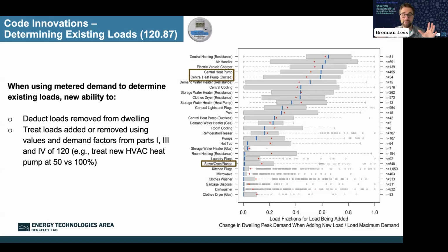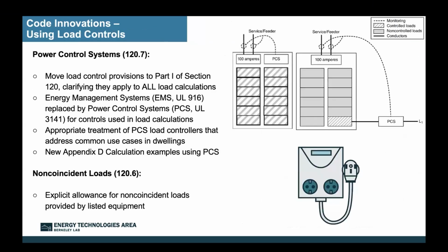Rather than having to add your new heat pump at 100% of its nameplate rating, we can look back at that section 120.87 we were just talking about and instead add it at 50%. Same goes for if you're adding a new electric cooker: instead of adding it at 12 kW, we can add it at 6 kW. So really big movement in terms of how loads are accounted for when using this metered demand method. I think this has the potential to really open up the loads we're able to safely add to existing dwellings.